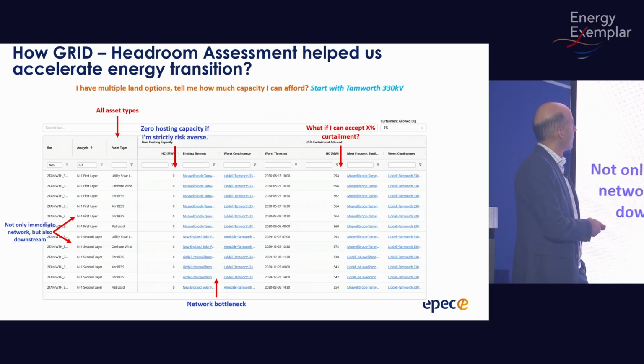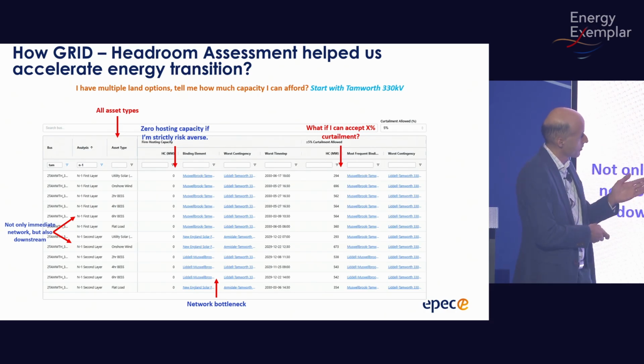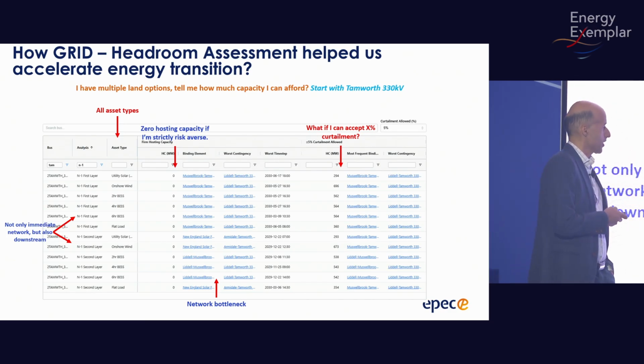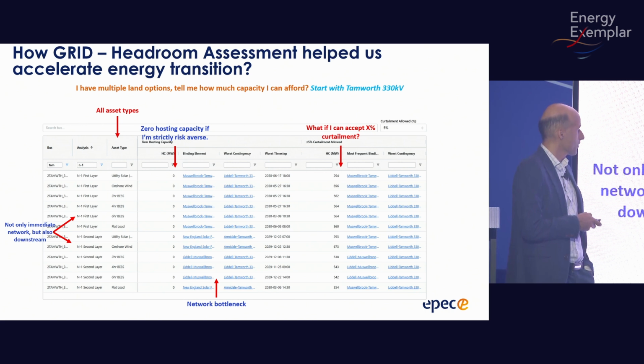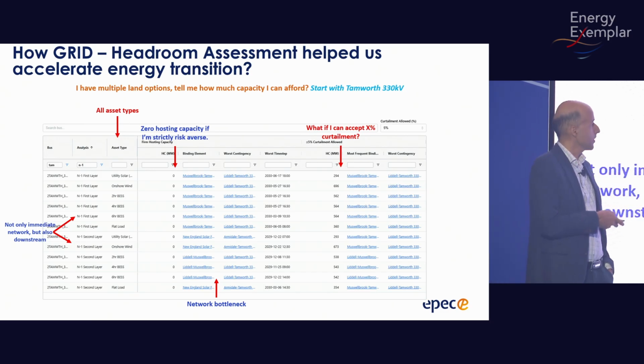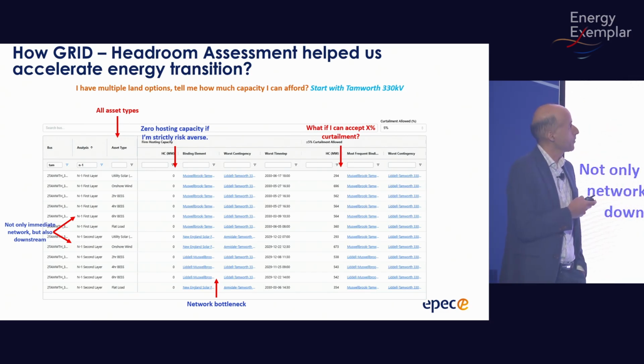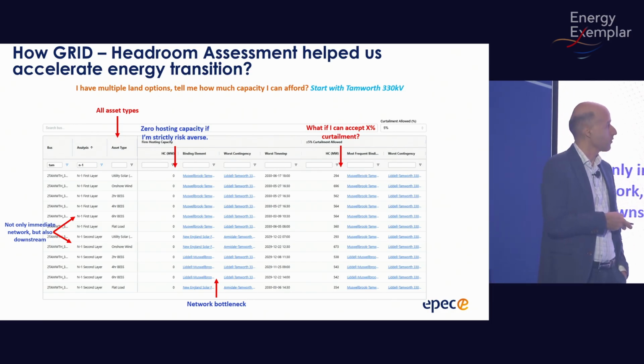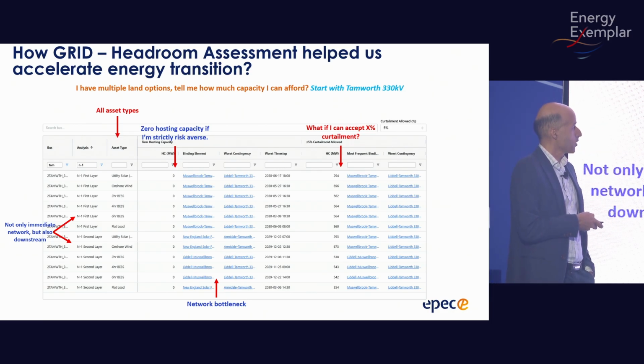Looking at injecting at Tamworth, we consider the N-1 first layer - all the lines connected to Tamworth - and the second layer, the downstream constraints. Different technologies: solar, wind, 2-hour storage, I should add 8-hour too, and data center type loads for different layers. If I'm too strict with curtailment - no curtailment allowed - there's no hosting capacity at Tamworth. But I'm not a developer, and developers typically take some risks.